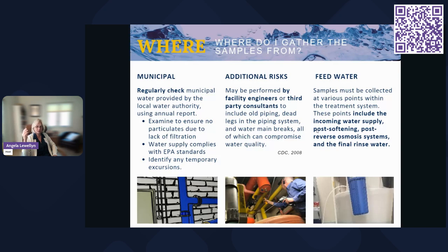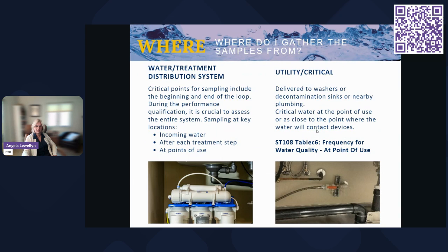We went to one hospital where a water main break a couple blocks away affected the water supply. So we're going to check and contact the city to see what's going on in your city as well. There's also feed water that should be collected at various points in the treatment system, after it's softened, and after RO or DI, at the point where that feed water becomes the final rinse water, which you can test at your third bay sink.